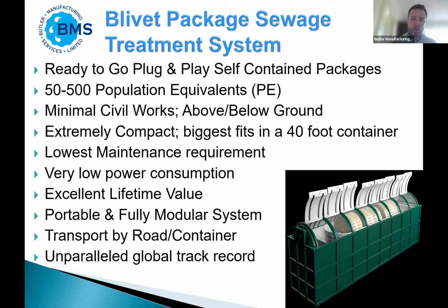It can slip into a 40-foot container for transport, which is really important for any international projects. Any projects in Europe, it can be road transportable, ready to go. It needs an hour per week of maintenance. Very low power consumption, even for 500 people, it's only 15 kilowatt hours per day.